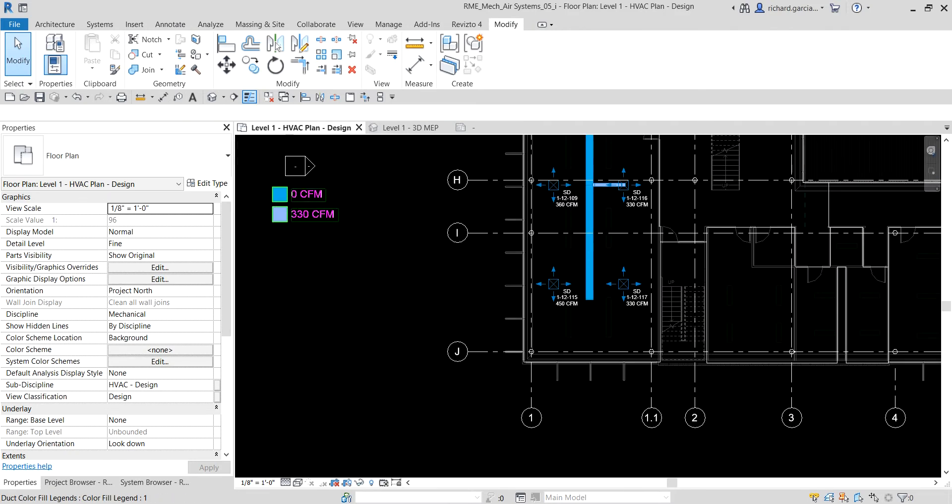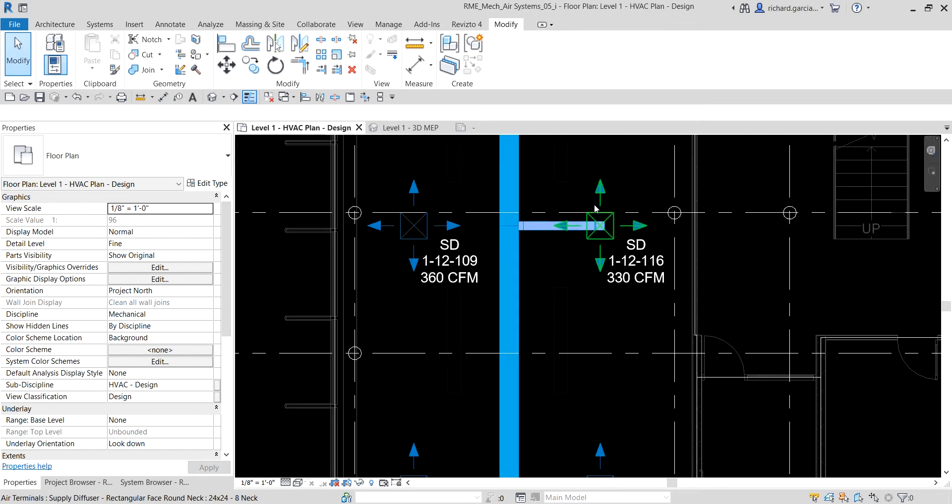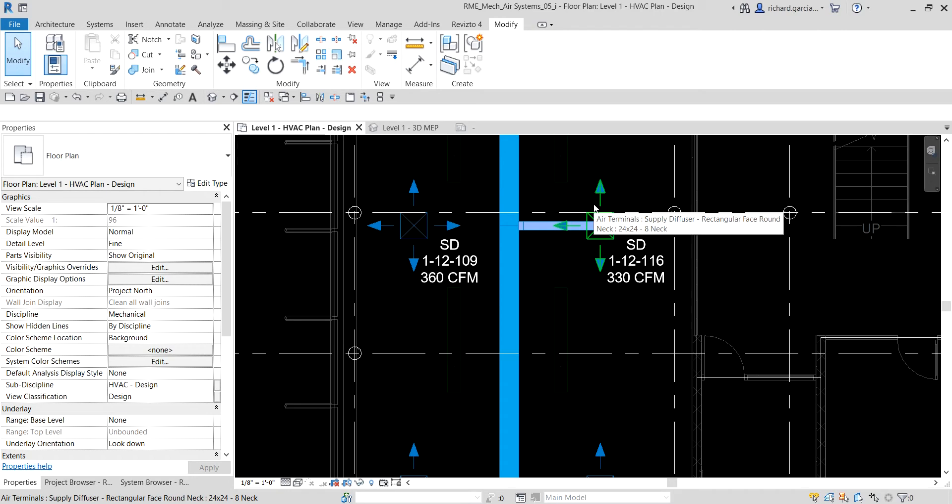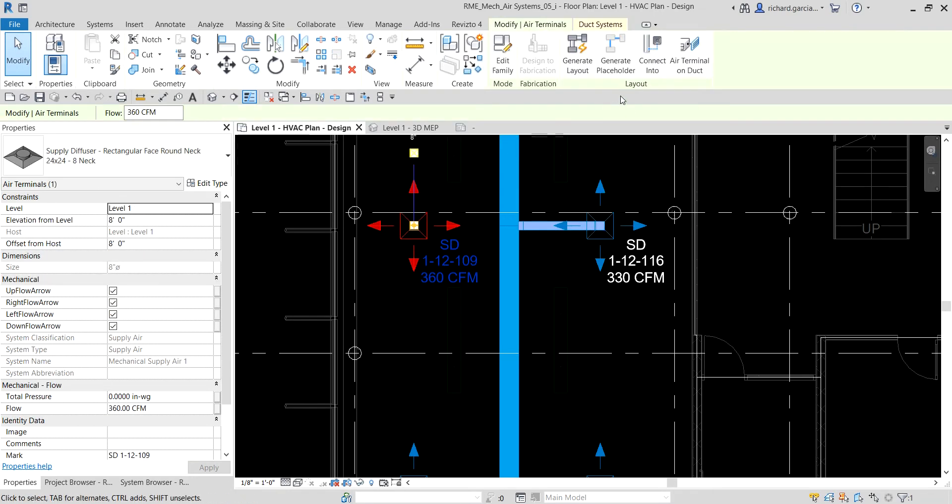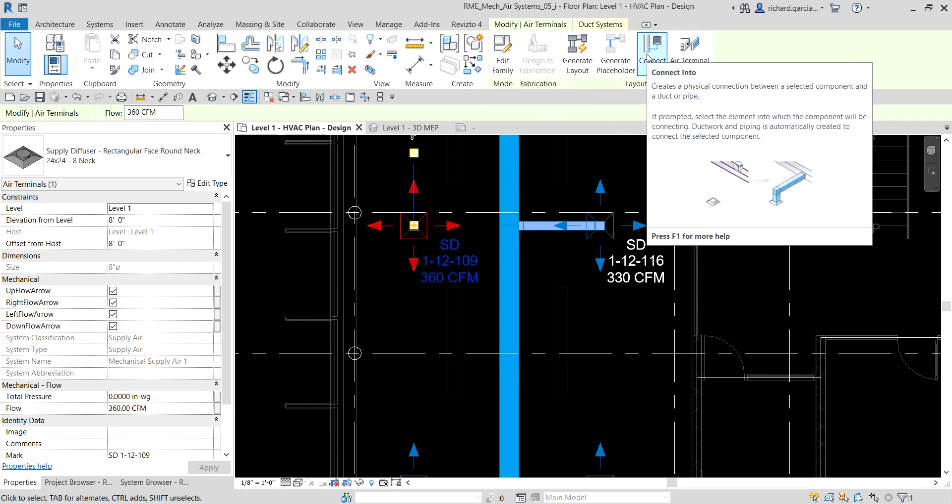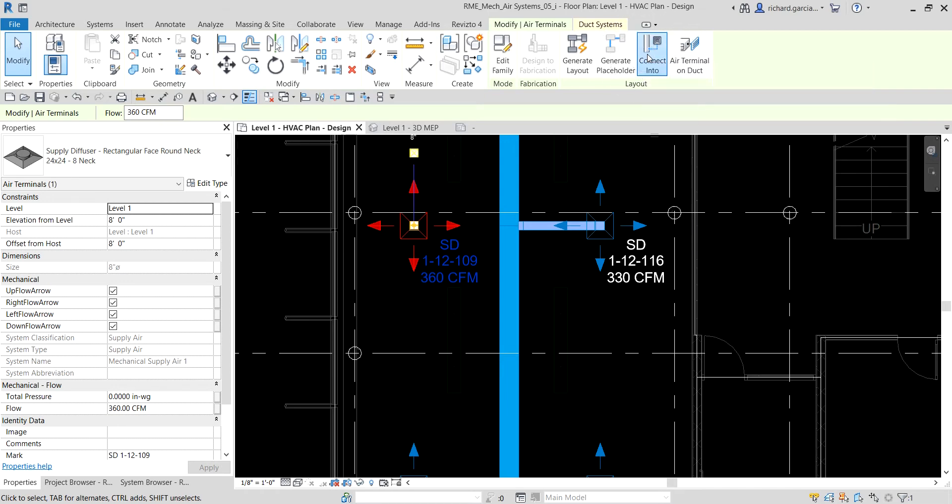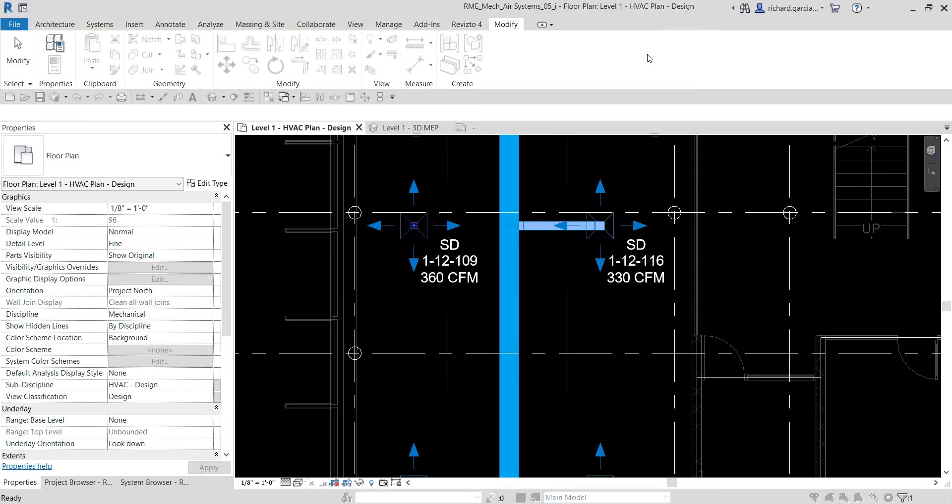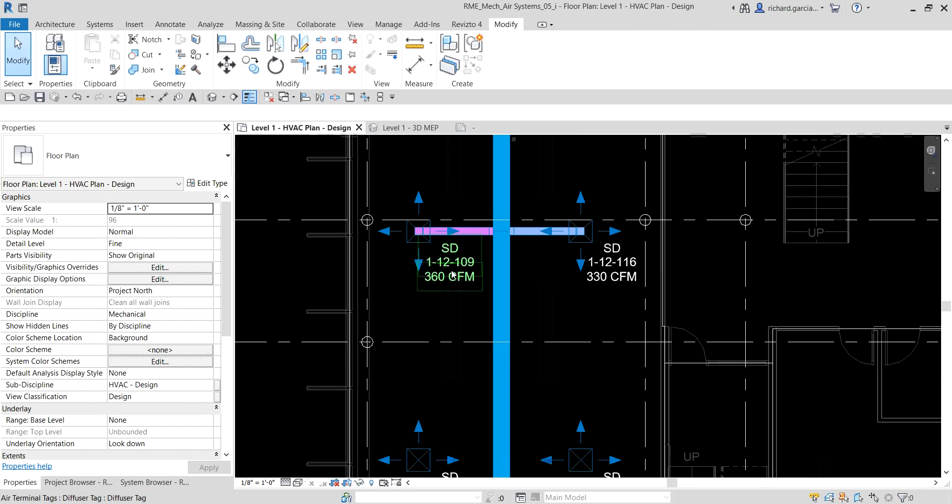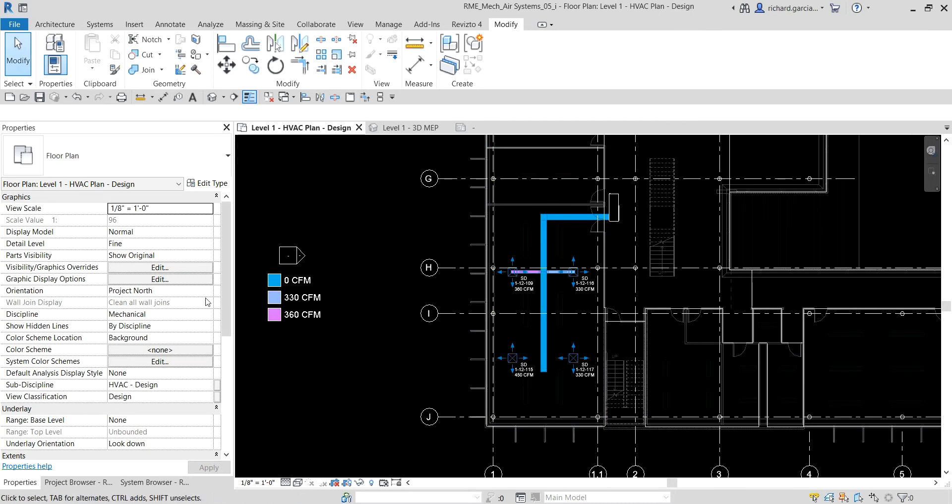Next, aside from doing that to create your duct, one useful tool you can use is Connect Into. The Connect Into tool is used to add or connect components to an existing air system. Note you can also use this when connecting your plumbing fixtures to a pipe. I'm going to select this air terminal, and then from the layout panel you can see Connect Into. It creates a physical connection between a selected component and a duct or pipe. I'm going to select this one, and then click your main duct here, and Revit will connect that automatically.